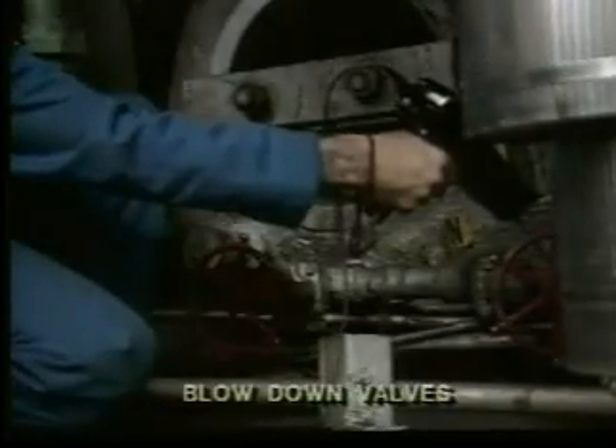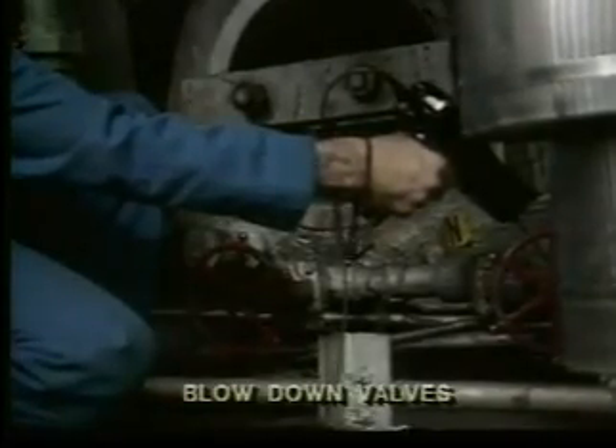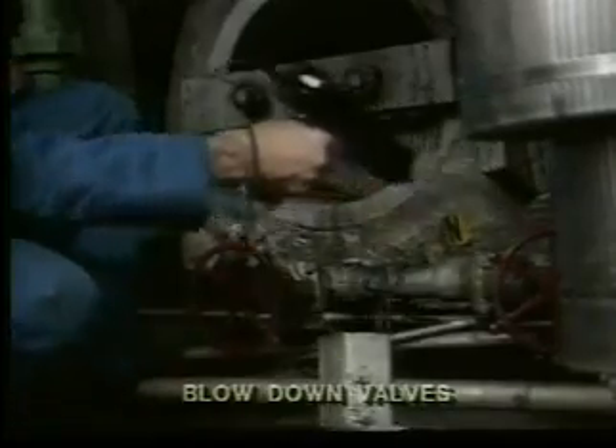Sometimes you may need to use the rubber probe. Adjust for background noise which may interfere. Blowdown valves are checked by using the contact probe on the downstream side. There should be no flow.